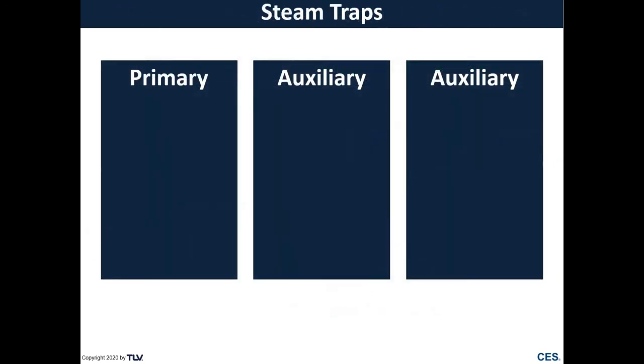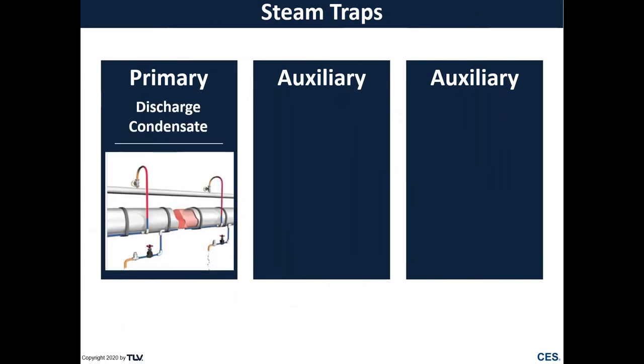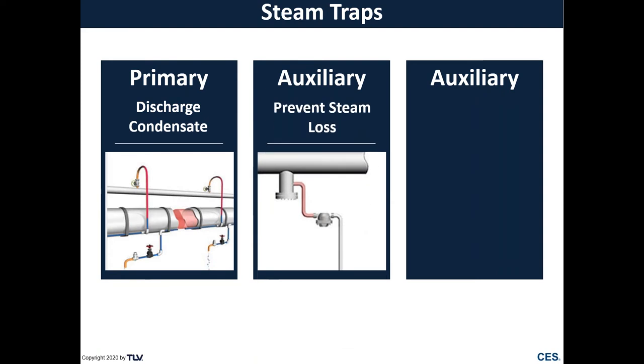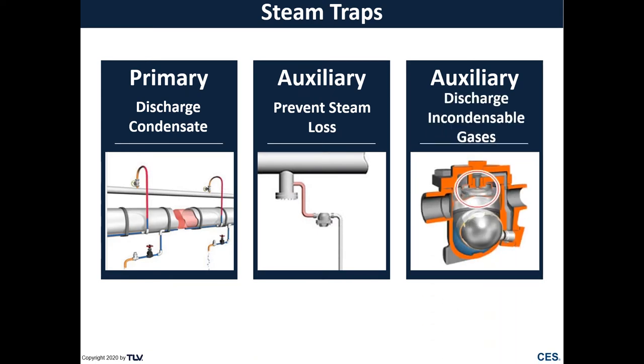There are three main functions of a steam trap. First, to discharge condensate from the steam system. After discharging condensate from the steam system, that trap needs to be able to shut off tightly in order to prevent steam loss. And last, discharge any incondensable gases. So there might be leftover air from your startup situation.